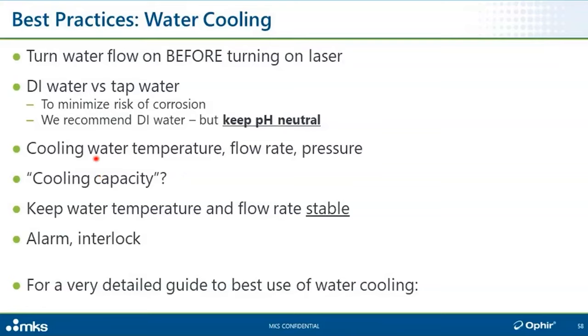We don't really recommend a specific chiller. The only thing that we care about, we're quite forgiving in terms of the details of the chiller. The main thing is that the chiller should have the capacity to remove the number of watts from the cooling water that you're going to be putting into it from your laser. So if you're going to be measuring a 10 kilowatt laser, make sure your chiller can remove heat at least at a rate of 10 kilowatts from the water.